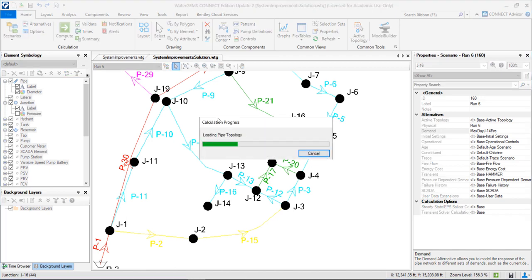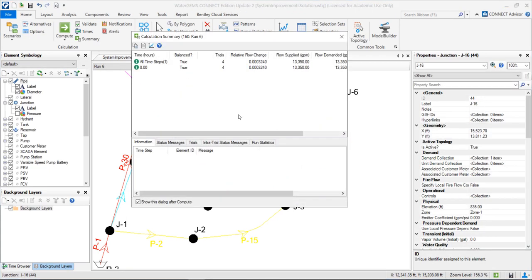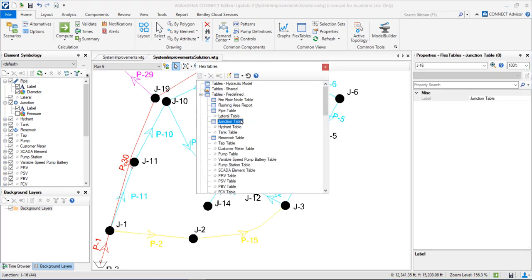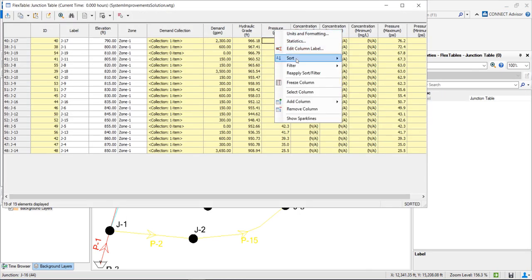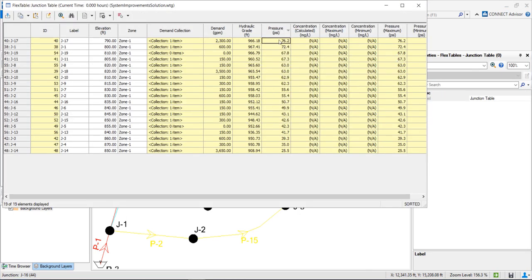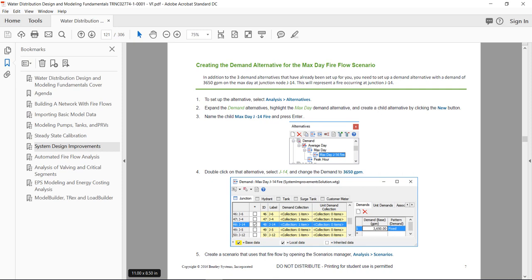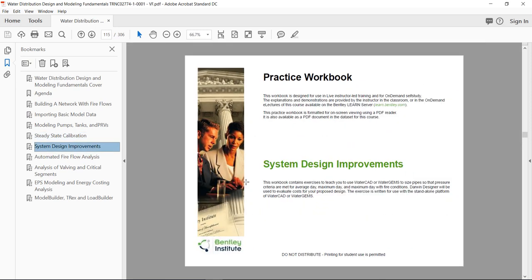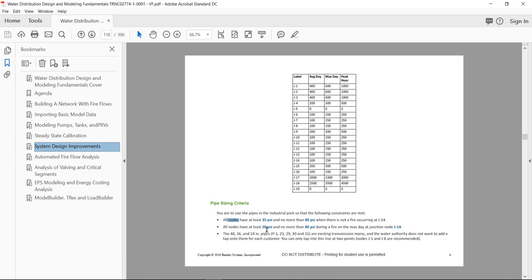Now we have the maximum day with fire flow associated to this scenario. We compute, then go to the flex tables, the junction table, sort ascending, and see that the lowest pressure is 25 psi. The criteria was to have pressures more than 20 psi for the fire flow, so this is also achieved.